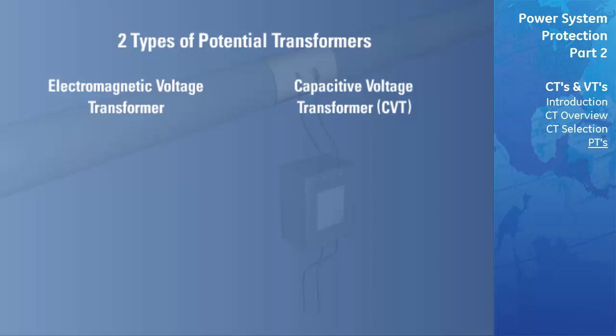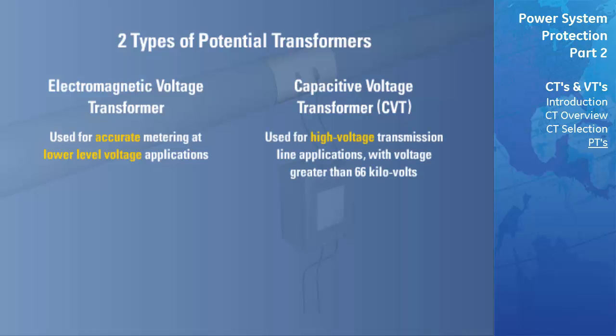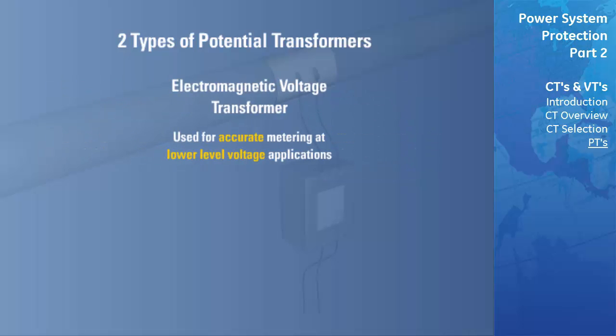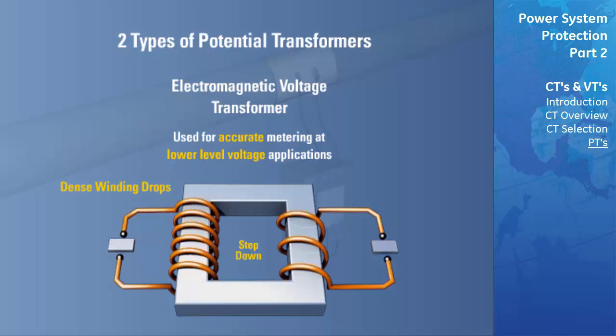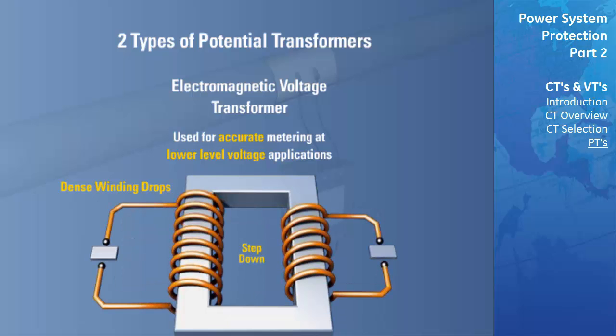Electromagnetic voltage transformers are usually used when accurate metering needs to be performed for lower voltage applications. Capacitive voltage transformers are commonly used in high voltage transmission line applications where the voltage is higher than 66 kilovolts. Electromagnetic voltage transformers have dense winding designs to accurately scale down the voltage and ensure the ratio is consistent for all variations in the input voltage. Due to the small amount of voltage drops per winding, electromagnetic voltage transformers will increase in size as the rated primary voltage increases. Likewise, the cost of electromagnetic voltage transformers tends to increase at a disproportionate rate to the primary voltage rating.